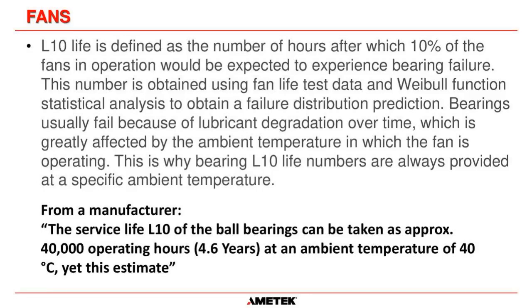And then at this bottom here, you can see from a manufacturer, the service life L10 of the ball bearings can be taken as approximately 40,000 hours. This was for, I think it was a Papst fan that I looked at. Yeah, it definitely was a Papst fan that I looked at. So 40,000 hours is 4.6 years, and that's at an average temperature of 40 degrees C. But they say, yes, this is an estimate, obviously. So once again, our designers looked at the fans that we use inside our systems.